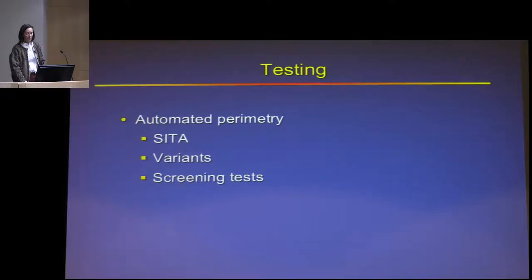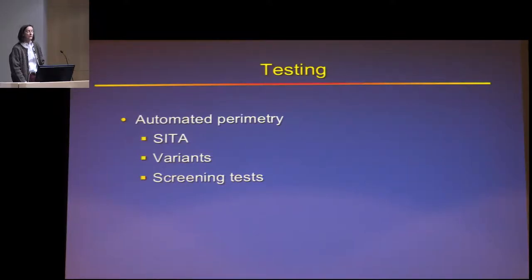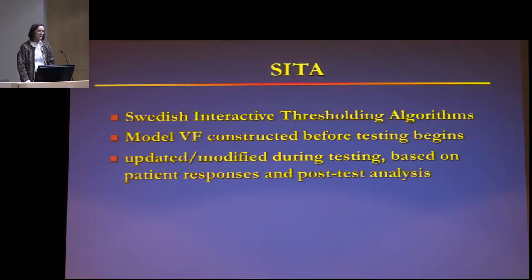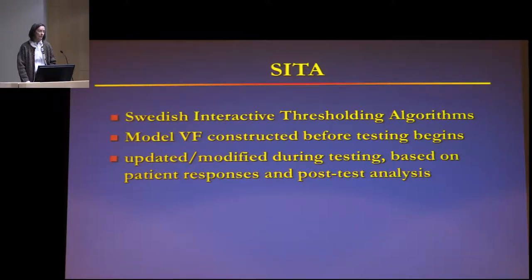Moving on to automated perimetry — almost everybody now uses some form of SITA. SITA stands for Swedish Interactive Threshold Algorithm. The machine assumes a certain visual field exists, then modifies and updates that estimate during testing. It does a few preliminary tests to decide how the patient is seeing and how quickly they're responding, then adjusts accordingly — unlike older methods where stimuli were presented at a fixed speed and brightness regardless of patient responses.